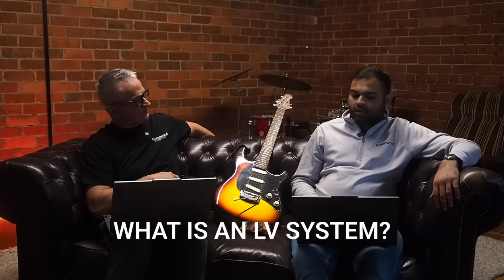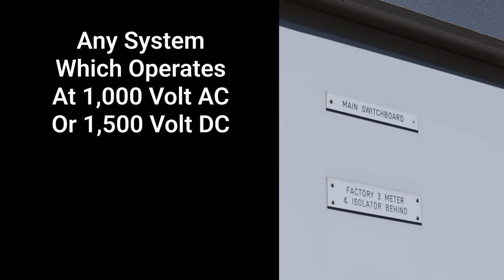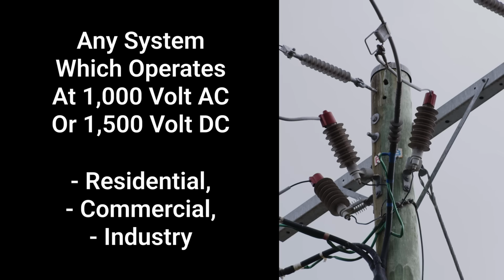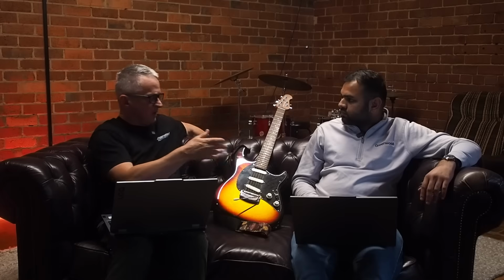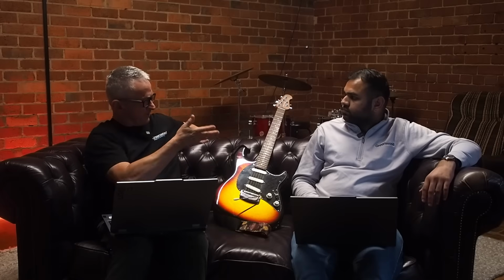So I suppose the first question, Jayesh, is what is the definition of an LV system? So basically the LV system is typically any system which operates at 1000 volt AC or 1500 volt DC. The supply which we usually see for residential, commercial or industrial systems. The 1500 volt DC obviously takes into consideration solar farms, because that's what they're operating on, those kinds of voltages.